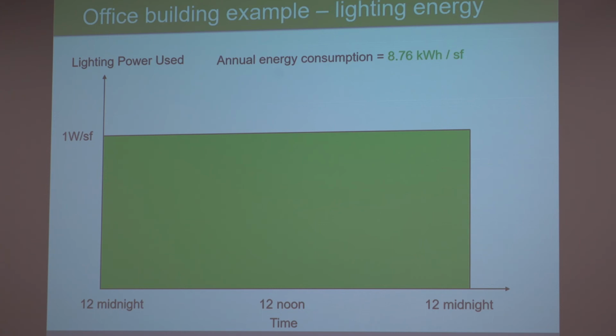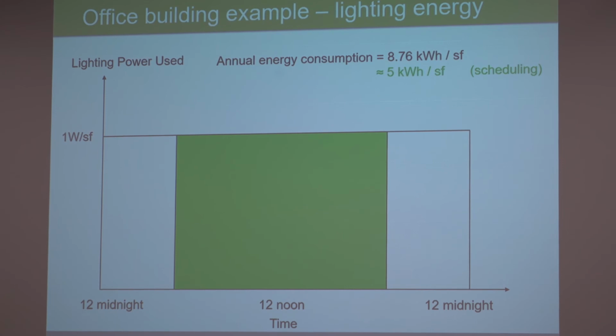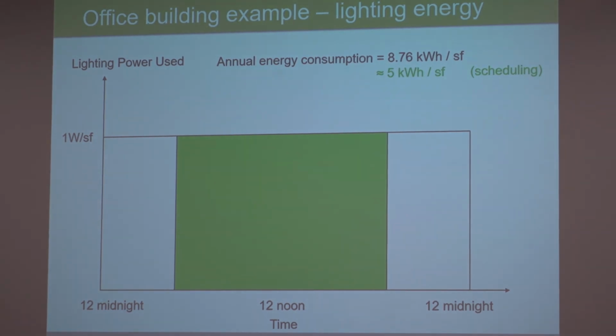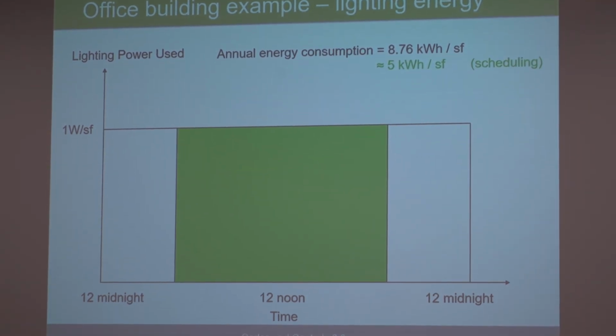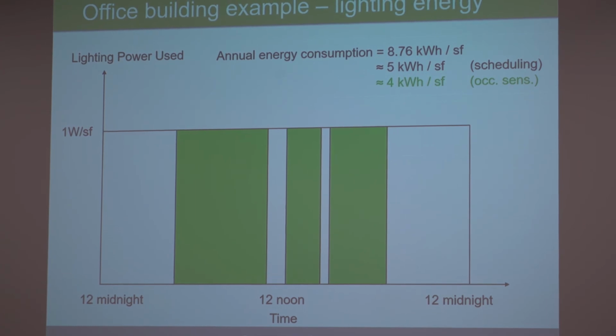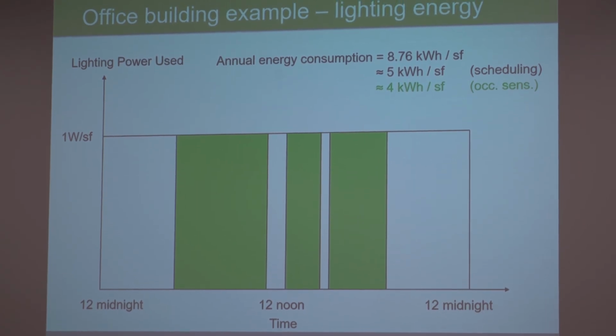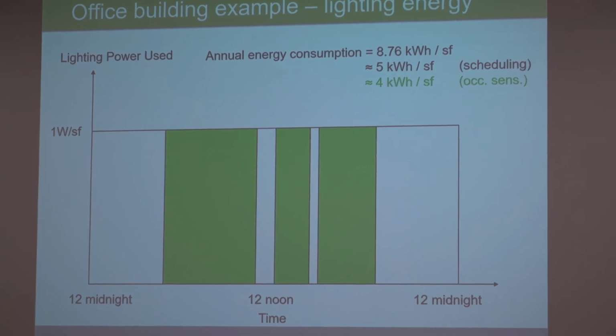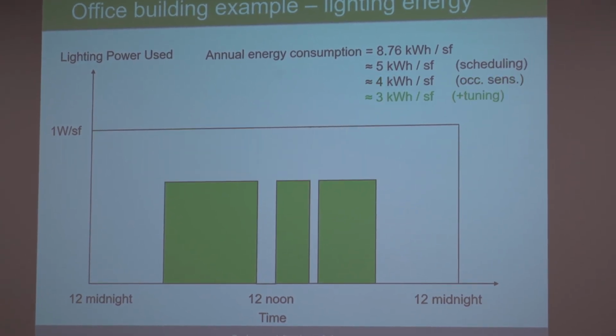If we lighted an office building to 1 watt per square foot, it would use 8.76 kilowatt hours a square foot of lighting energy in a year. Okay, we just lighted up to that level. Then we throw in the scheduling and we sweep the lights off during the non-operating hours. Now you're down to about 5 kilowatt hours per square foot in a year. You do occupant sensing. You're turning lights off when the spaces are empty. Now you're down to about 4 kWh per square foot of lighting power in a year.